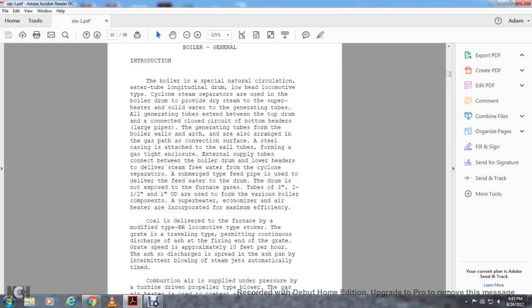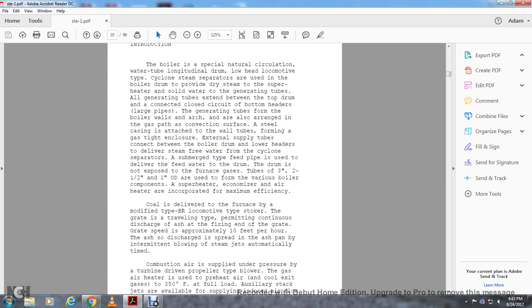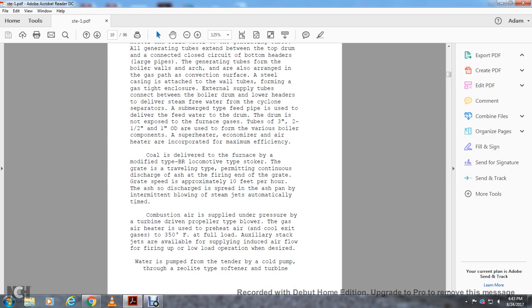Superheater, economizer and air heater, incorporated with the maximum efficiency. Coal is delivered into the furnace by a modified type BR locomotive type stoker. The grate is a traveling type, permitting continuous discharge of ash at the firing end of the grate. Grate speed is approximately 10 feet per hour. Ash discharge is spread with the ash pan, intermittently blowing steam jets, automatically timing combustion air is supplied under pressure by a turbine driven propeller type blower.